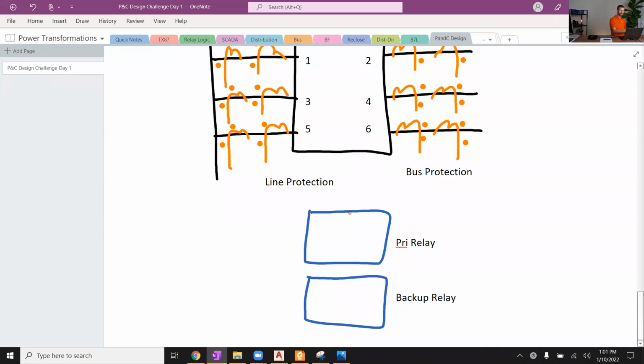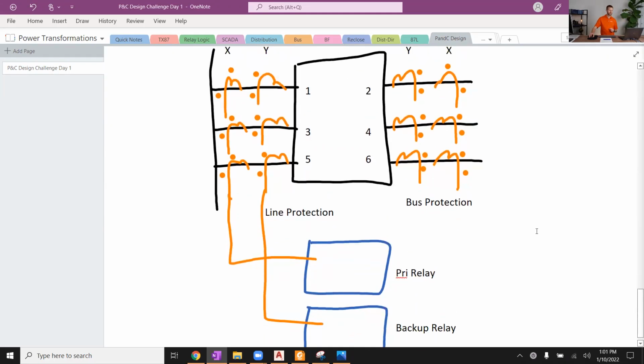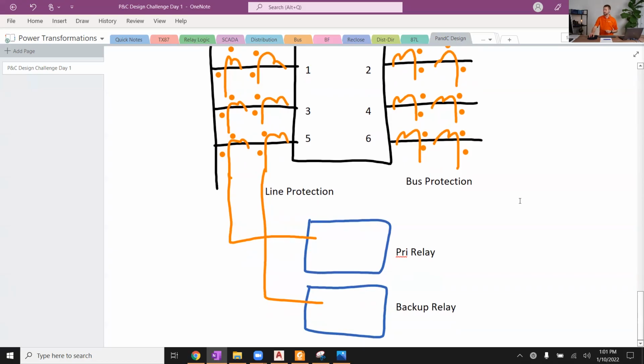Usually we do our primary on the outer X, and then our backup on our inner Y bushing CT. And so these actually are not going to be in series with one another. They're going to be going to separate relays to provide a level of redundancy. I think Sean jumped in there and answered that, so thank you for participating.